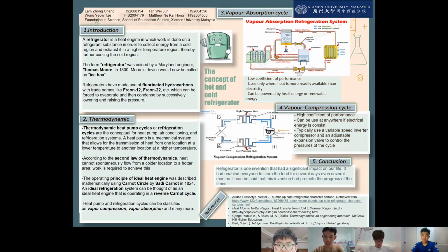The vapor compression cycle is used by many refrigeration, air conditioning, and other cooling applications, and also within heat pumps for heating applications. There are two heat exchangers, one being the condenser, which is hotter and releases heat, and the other being the evaporator, which is colder and accepts heat. For applications which need to operate in both heating and cooling mode, a reversing valve is used to switch the roles of these two heat exchangers.